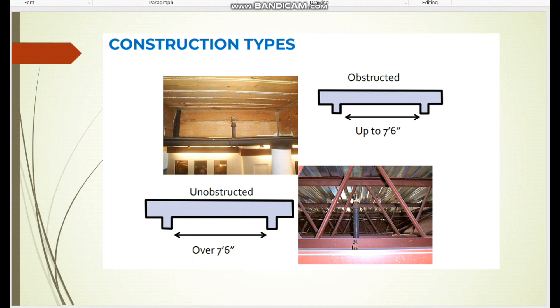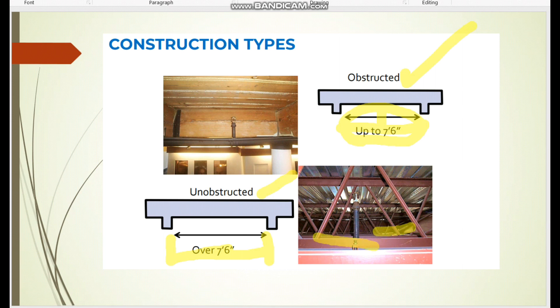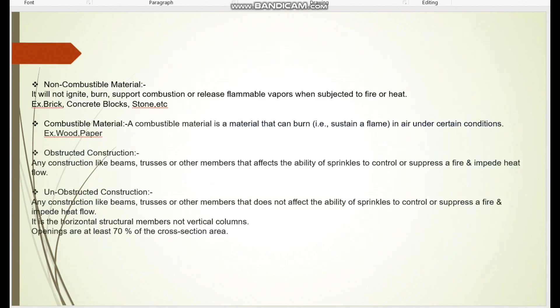As shown in this image, obstructed construction means the distance between one structural member and another structural member is up to seven feet six inches. If it is more than seven feet six inches, then it is unobstructed construction. An important note is that this applies to horizontal structural members, not vertical columns. Also, openings must be at least 70% of the cross-sectional area.